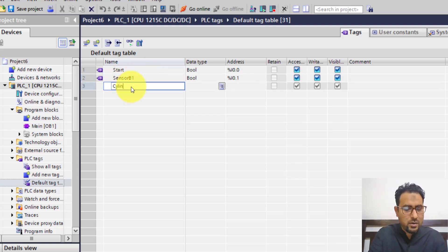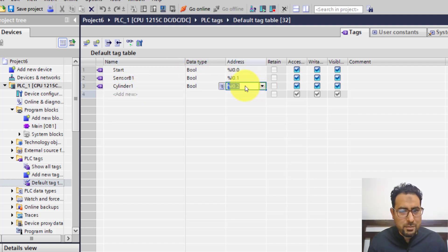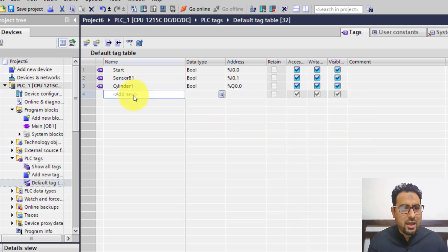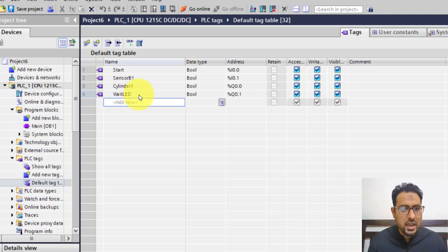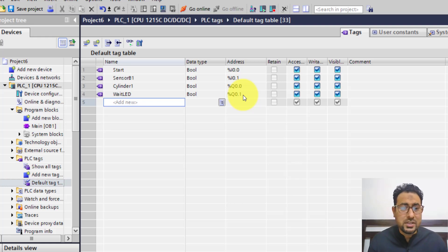After that, I need a cylinder 1 output. So it is cylinder 1 and this time it is going to be an output, with an output address at bit 0. Then I also need a wait LED as an output. Apart from these, I need timer settings as well. For stamping time, I need a preset value of 4 seconds; for waiting time, 20 seconds; and for the counter, a preset value of 10.